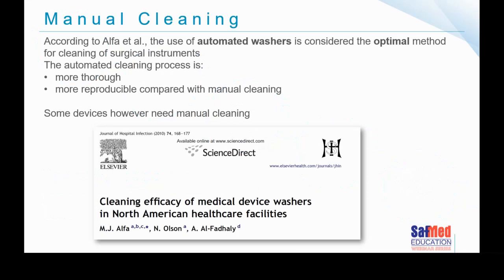We opened with this slide in our previous session on cleaning. This paper by Alfa, published in 2010, explains that the optimal method of cleaning is to clean devices in an automated washer disinfector. Why? Because it's more thorough and more reproducible compared with manual cleaning. We do know that some devices will need to be cleaned manually.